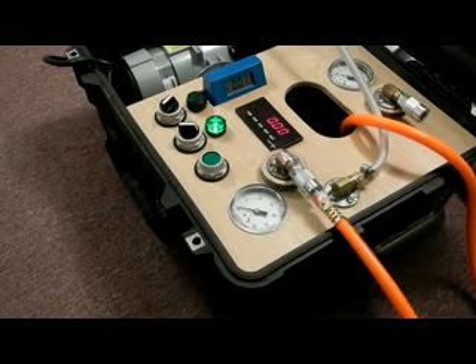This little video demonstrates the use and calibration of the void measuring equipment. What we're seeing right now is there's no pressure in the system. The meters have been turned on to warm up. The large meter in the middle, which is reading 0.00 in the red letters, is the totalizer or actual volume. The blue meter sticking up through the panel is the flow sensor itself, and that is reading flow in liters and is just used as a reference.